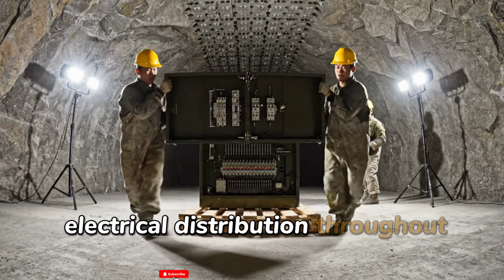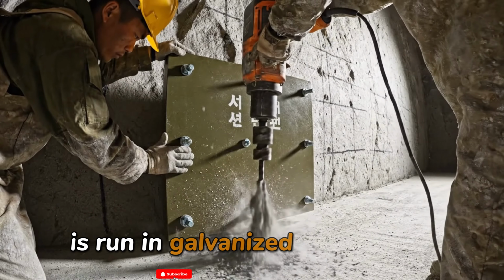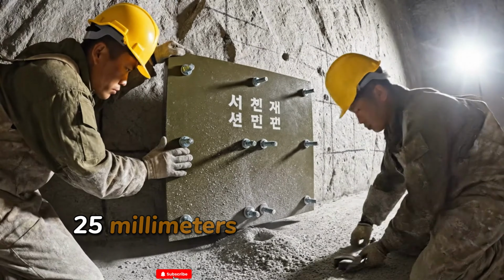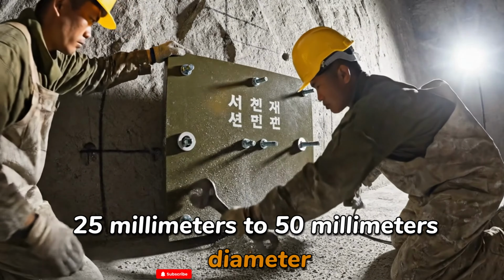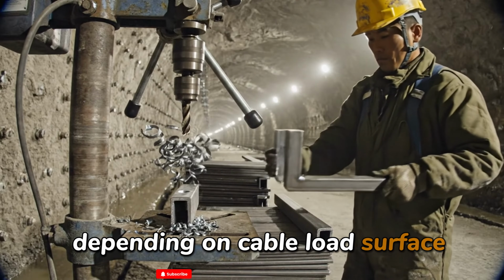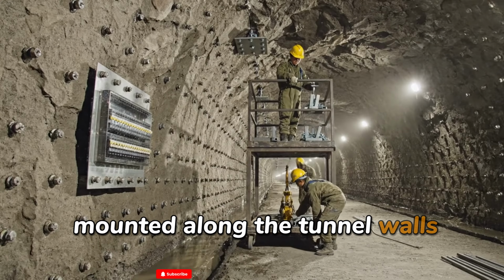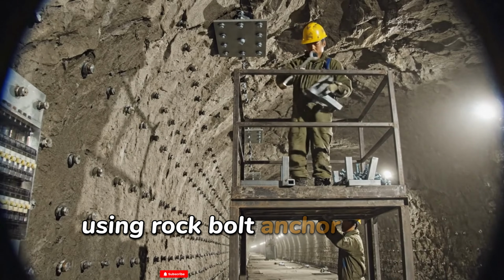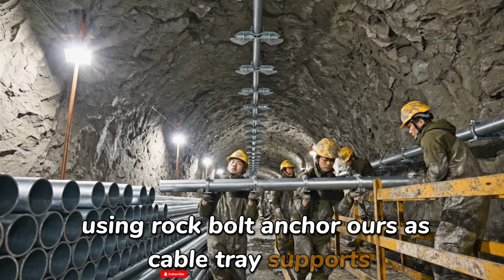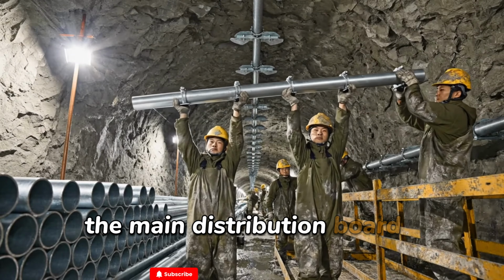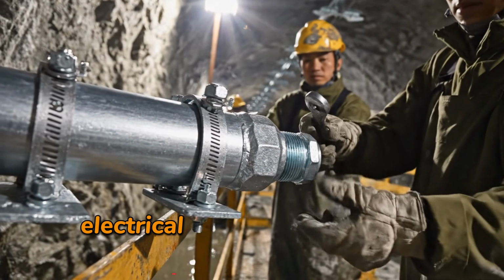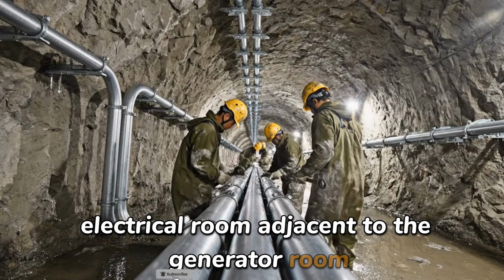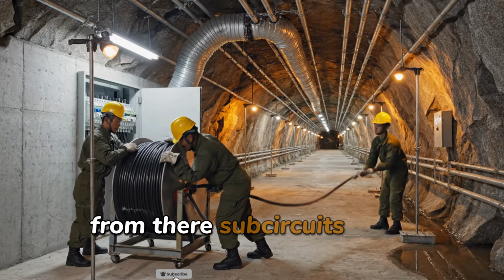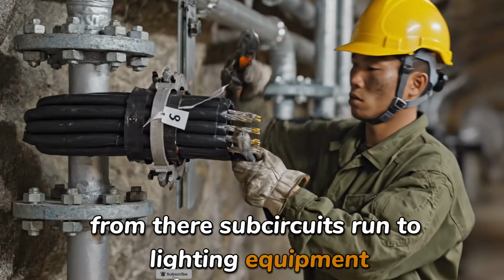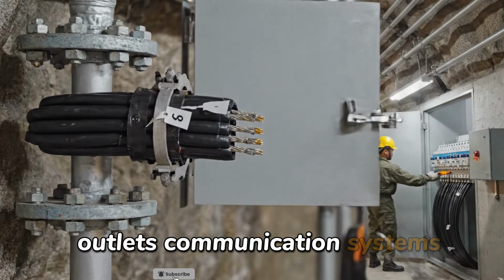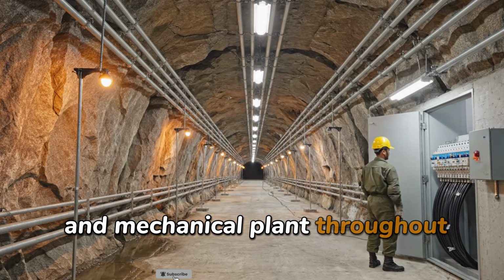Electrical distribution throughout the bunker is run in galvanized steel conduit, 25 mm to 50 mm in diameter depending on cable load, surface mounted along the tunnel walls and ceiling using rock bolt anchors as cable tray supports. The main distribution board is located in a sealed electrical room adjacent to the generator room. From there, sub-circuits run to lighting, equipment outlets, communication systems, and mechanical plant throughout the bunker.